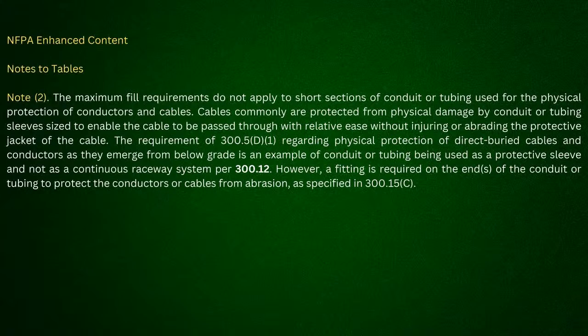Mm-hmm. So a lot of that stuff is kind of the behind the scenes math that me and King James might not be sharing with you guys while we're doing this and talking about it. But when it's just a sleeve, you have these tray cables that a lot of times we're oversizing that sleeve anyway. We want it to be easy to pull through. But we're running like a 2-inch with like 10 cables in it, and so the fill is not required, but you have so much displacement of that air from transferring from a sleeve to free air that you're not going to build up bundling heat in there.